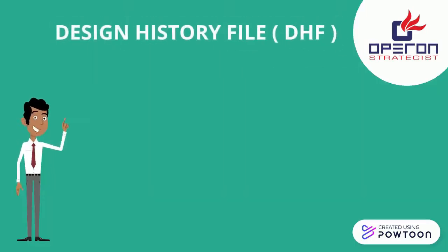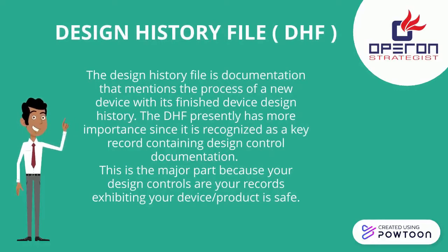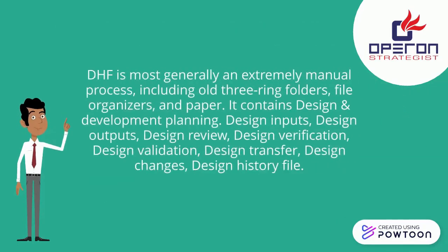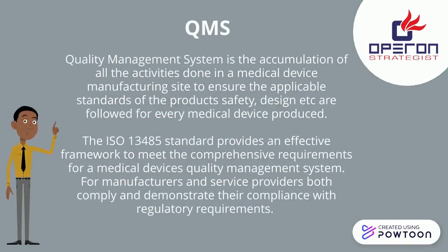Design history file, DHF. The design history file is documentation that mentions the process of a new device with its finished device design history. The DHF presently has more importance since it is recognized as a key record containing design control documentation. This is the major part because your design controls are your records exhibiting your device/product is safe. DHF is most generally an extremely manual process, including old 3-ring folders, file organizers, and paper. It contains design and development planning, design inputs, design outputs, design review, design verification, design validation, design transfer, design changes, design history file.